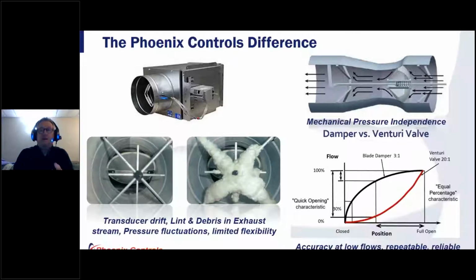Now that's very different with the mechanical pressure independence of the Venturi valve. The mechanical pressure independence has a cone and funnel assembly inside the middle of that Venturi, right? And within that cone and funnel is a spring. That spring inside there compensates for any of those fluctuations in pressure that you might see in that ductwork. And so stable directional flow takes away that risk, right, of compromising pressure. So for any pressure fluctuation, it neutralizes that and goes straight to position, finds the flow that it's needed, and accommodates that instantly, right, with that spring.